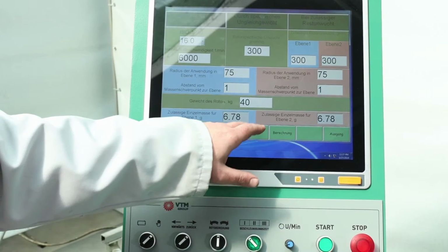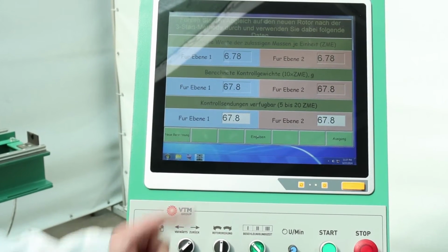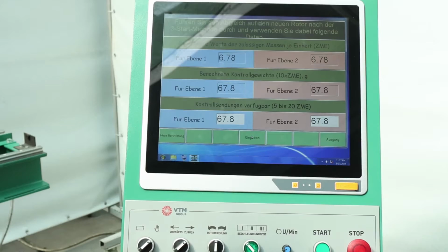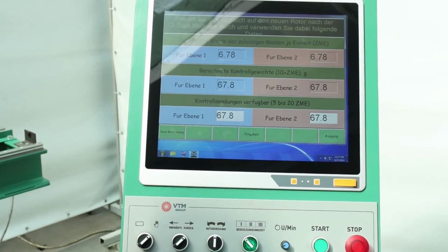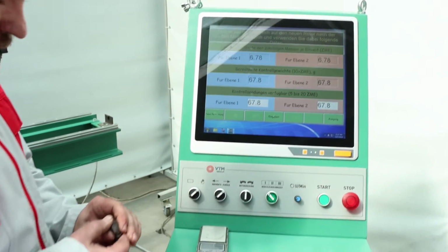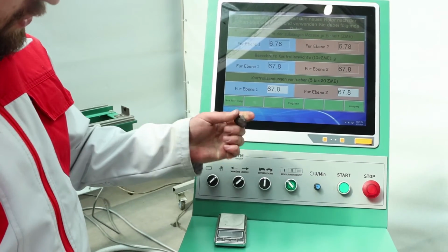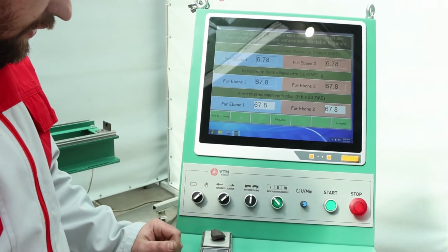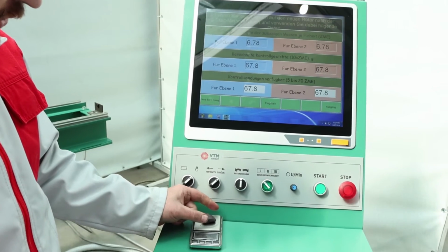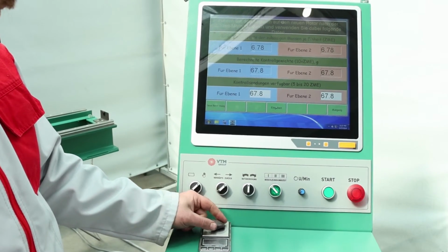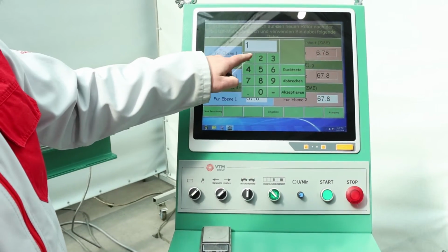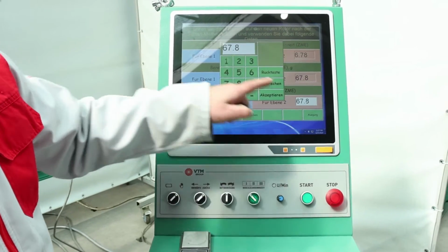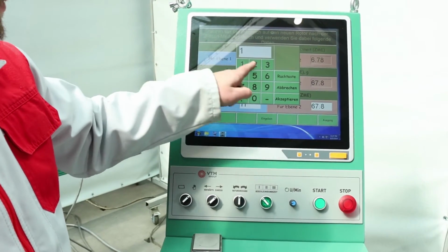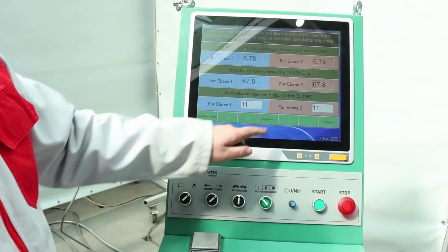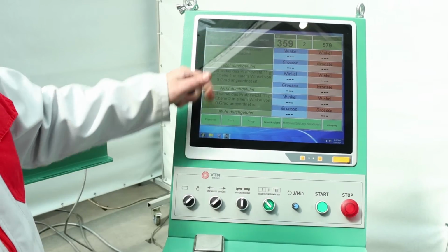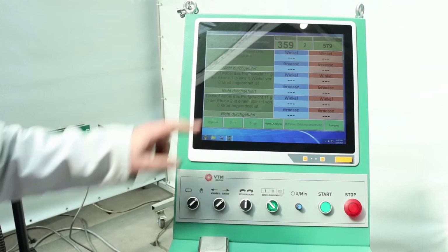Next, we will press the accept button. And in this section, we're going to set the mass of our calibration weight. We use plasticine for this. Put it on the scale, we see that our calibration weight is 11 grams. Set it to 11 grams. Press accept. And then we do 3 launches.